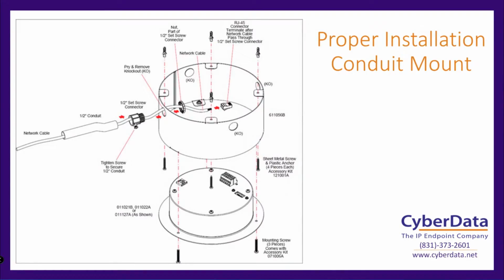With conduit mounting, we recommend a 1/2-inch conduit, but there are other ways. You could get a connector and go from a 3/4-inch, a 1/4-inch, or even an inch conduit to taper down into a 1/2-inch conduit. But for the actual connector to connect to the conduit mount itself, you will need a 1/2-inch connector, which is supplied.